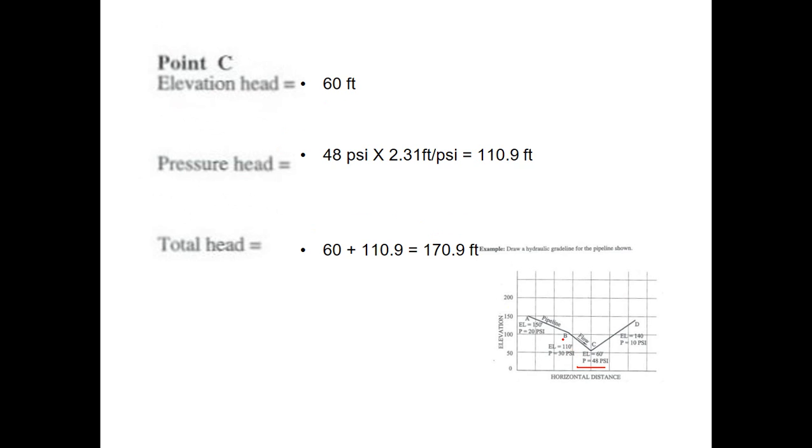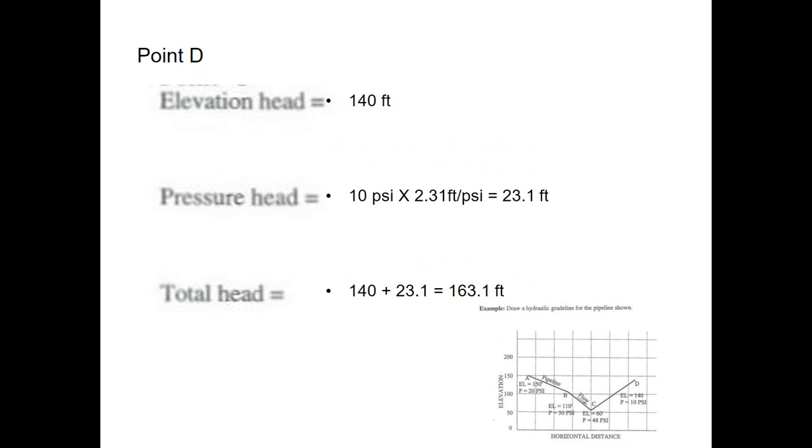Here we've got the pipe dropping down to 60 feet. The pressure goes up to 48. Convert that into feet, that's 110.9. Add that to 60, you get 170.9. And then the last one is at 140 feet.